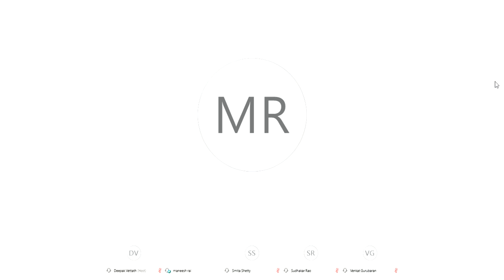So on the table, you check the threshold, at what minimum output the ventricle captures. That is called the threshold voltage, the minimum voltage required to generate a ventricular capture. And the pacemaker is programmed to more than twice the threshold output. Okay, so if the threshold is 1.5, we program the pacemaker around 2.2, 2.5 or 3. Not less than that, just to keep a safety margin of around twice.